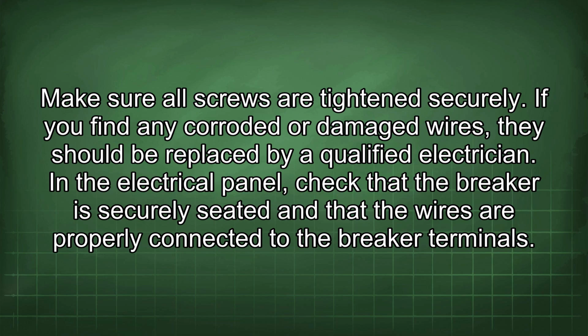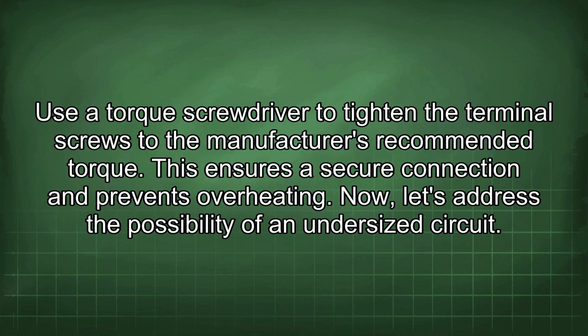In the electrical panel, check that the breaker is securely seated and that the wires are properly connected to the breaker terminals. Use a torque screwdriver to tighten the terminal screws to the manufacturer's recommended torque. This ensures a secure connection and prevents overheating.